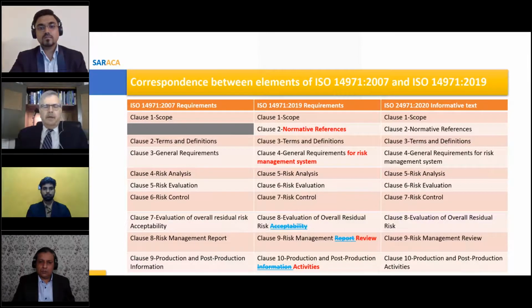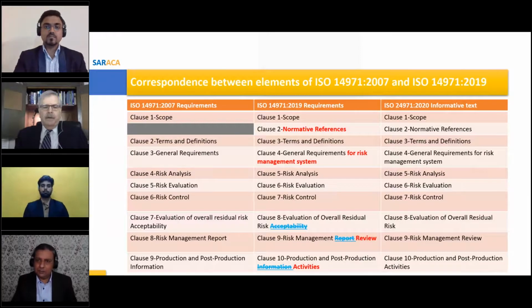The other thing that has changed is that the risk analysis that's been done in the past has always been done in fault conditions. However, the new 2019 refers to normal and fault conditions, which will require additional risk analysis measures to be used to do the risk analysis. And again, those can be found in the TR 24971. The other thing that I wanted to mention is that the definition of harm has been changed in the new standard. Physical harm has been removed and it just says harm. It's been expanded to include the environment and other forms of harm that were not considered in the past.